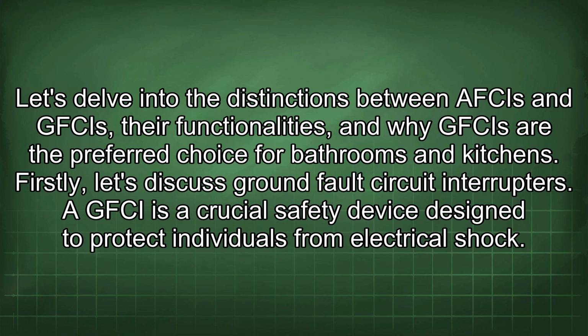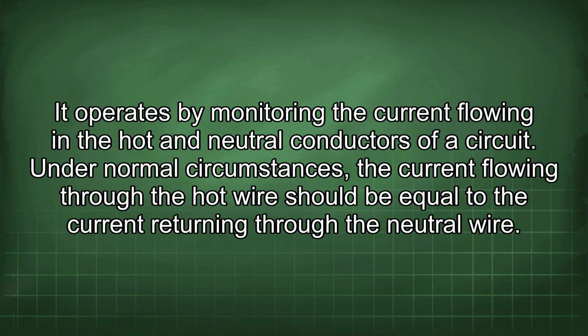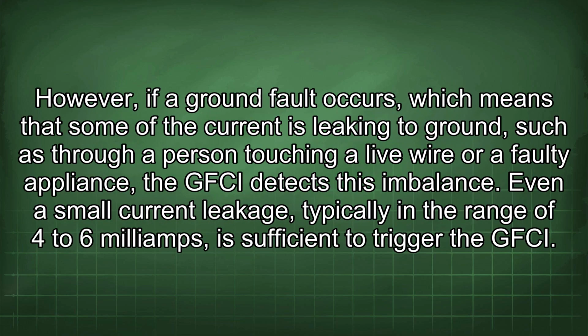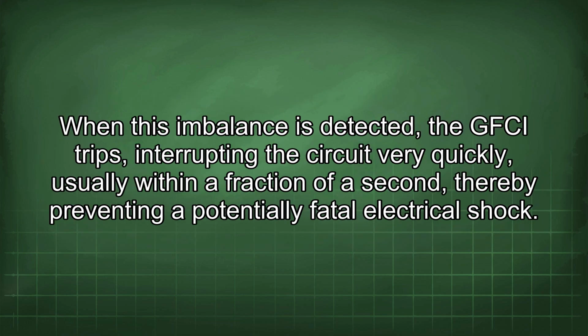A GFCI is a crucial safety device designed to protect individuals from electrical shock. It operates by monitoring the current flowing in the hot and neutral conductors of a circuit. Under normal circumstances, the current flowing through the hot wire should be equal to the current returning through the neutral wire. However, if a ground fault occurs, which means that some of the current is leaking to ground, such as through a person touching a live wire or a faulty appliance, the GFCI detects this imbalance. Even a small current leakage, typically in the range of 4 to 6 mA, is sufficient to trigger the GFCI. When this imbalance is detected, the GFCI trips, interrupting the circuit very quickly, usually within a fraction of a second, thereby preventing a potentially fatal electrical shock.